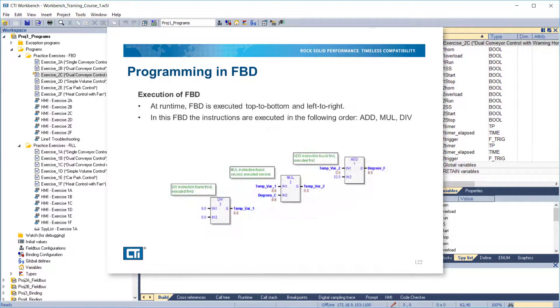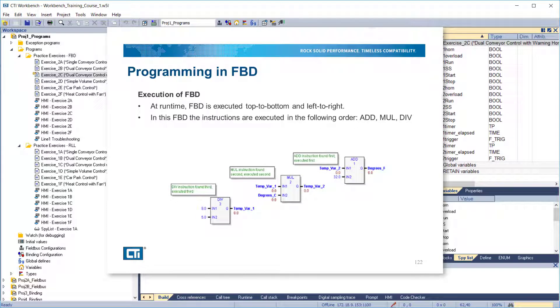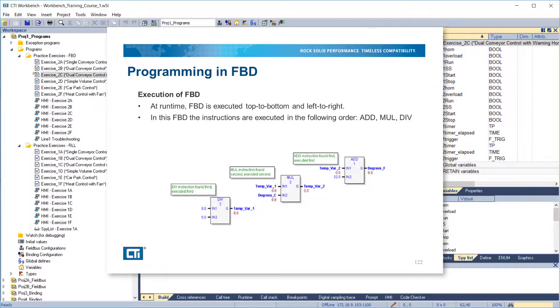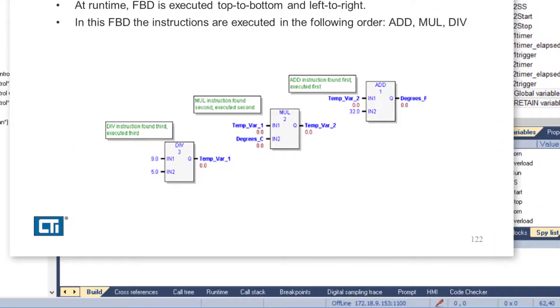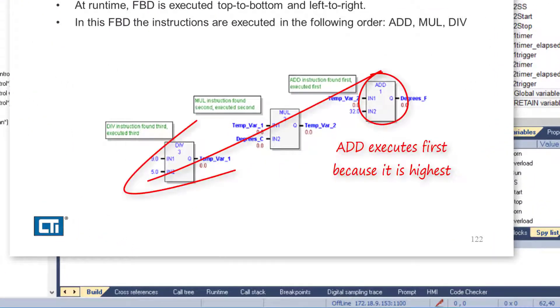During runtime, FBD is executed top to bottom and left to right. The higher object always executes first. If two blocks are at the same position vertically, then the leftmost block executes first. In this example, the instructions are executed in the following order: Add, Multiply, Divide.